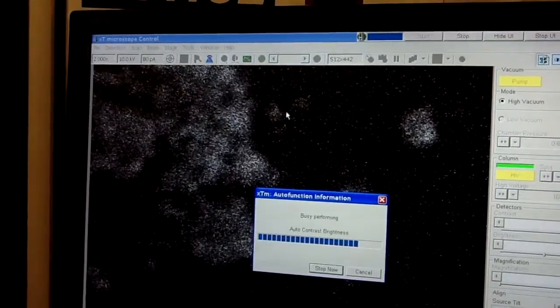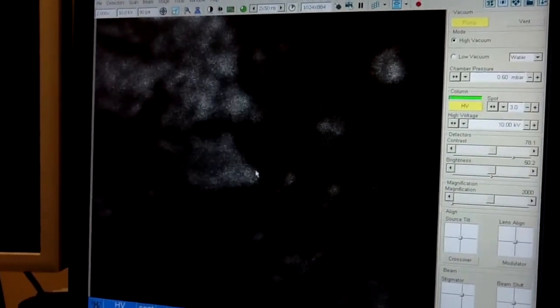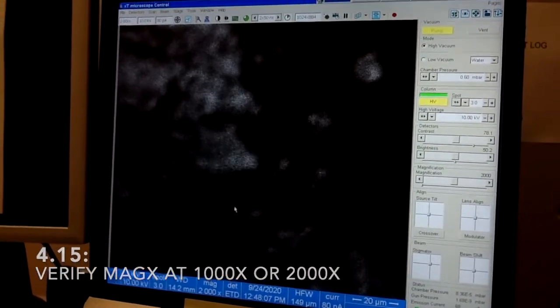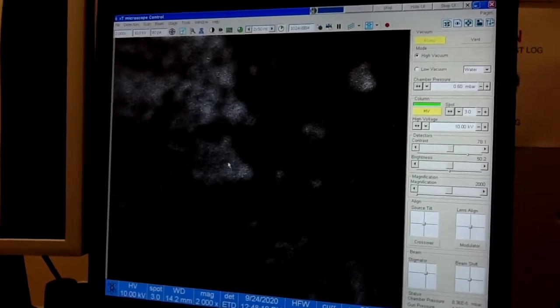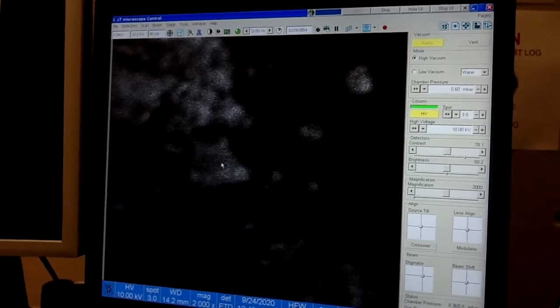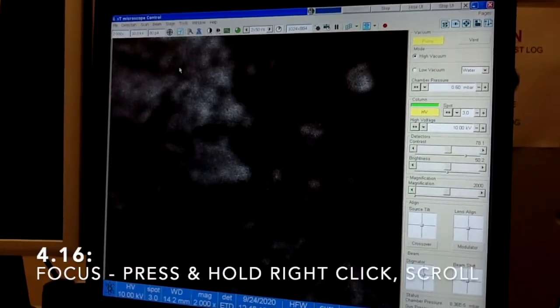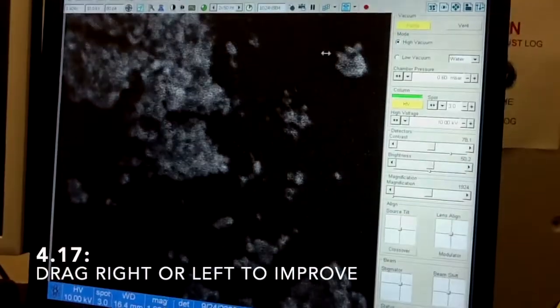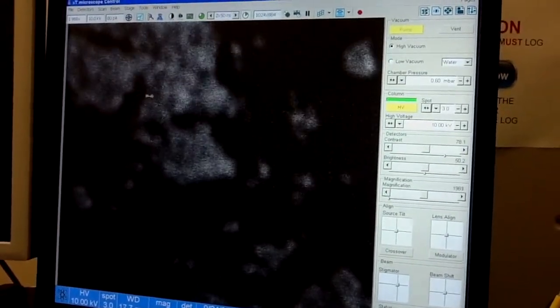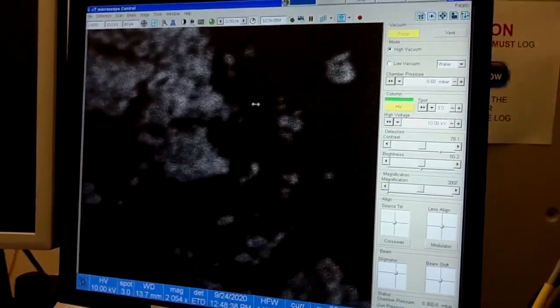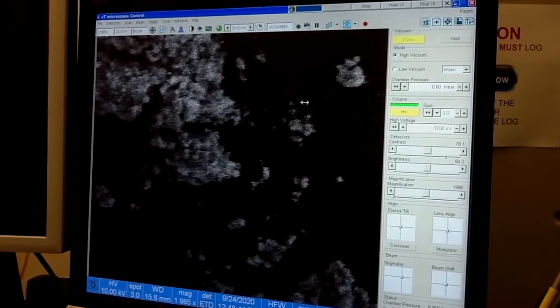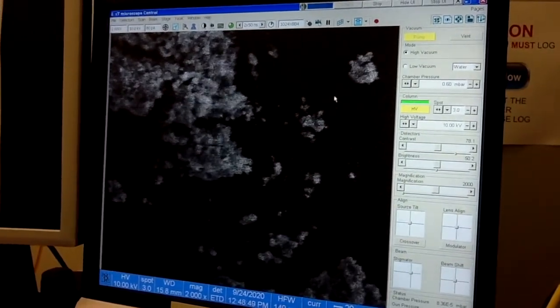Now initially the image will be out of focus, maybe very dark, but this is where you need to align it or adjust it. So first thing is to hit this auto contrast brightness button here. It will equalize your contrast. Now you can see a little bit more. Second thing, you want to image decent magnification. I have 2000 right now, but you can maybe even do it at 1000 or slightly higher. Around 1000, few 1000 will be okay. Focus the image. For focusing, press the right button on your mouse and just scroll right or to the left until you start to see that this image is in a better focus. It still won't be ideal, but we want to be close enough to go to the next step.